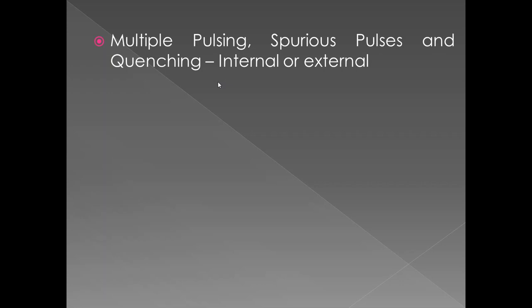Now, no longer do argon ions reach the cathode, because they transfer their charge to the bromine molecules. The bromine molecular ions now reach the cathode, and by accepting electrons from the cathode, they neutralize. However, these bromine molecular ions, the quenching ions of the quenching agent, on reaching the cathode and getting neutralized, even if they are in an excited state, they don't come down to the ground state by emitting photons like in the case of the argon ions.